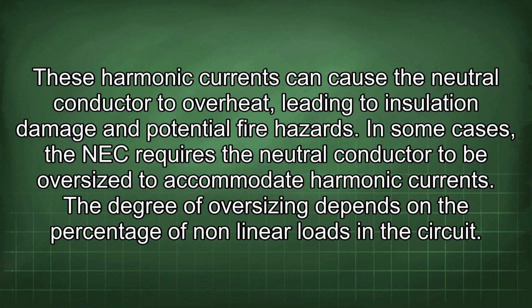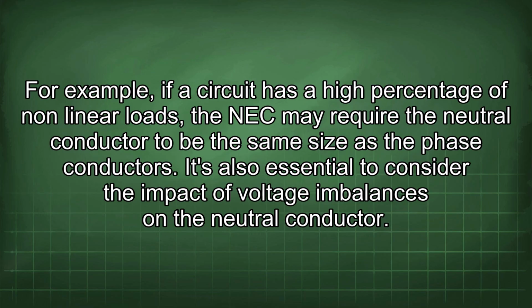In some cases, the NEC requires the neutral conductor to be oversized to accommodate harmonic currents. The degree of oversizing depends on the percentage of nonlinear loads in the circuit. For example, if a circuit has a high percentage of nonlinear loads, the NEC may require the neutral conductor to be the same size as the phase conductors.